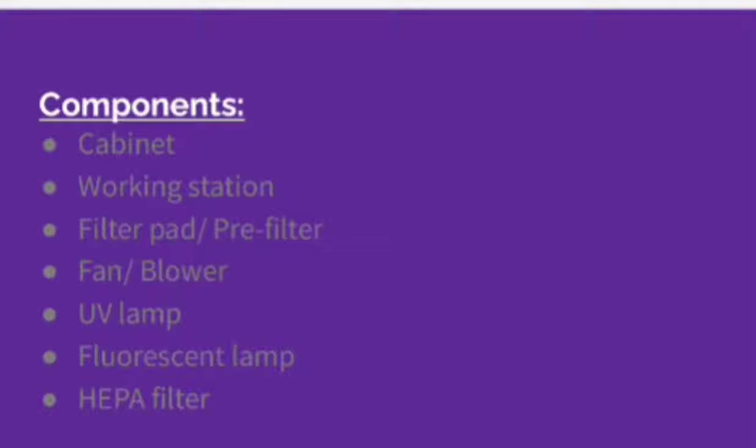Some laminar airflow cabinets might have a UV germicidal lamp that sterilizes the interior of the cabinet and contents before the operation. The UV lamp is to be turned on 15 minutes before the operation to prevent the exposure of UV to the body surface of the user.